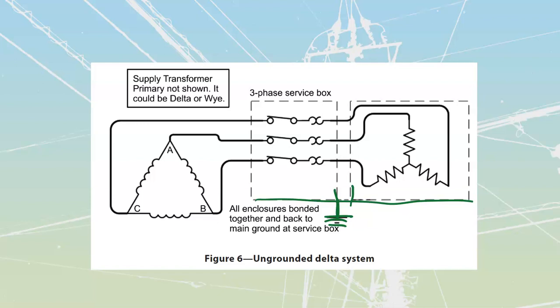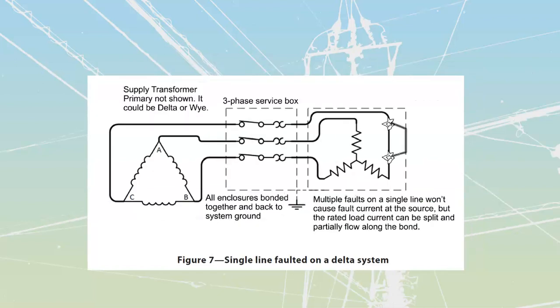Taking a look at what happens under a fault: if there's a single fault, absolutely nothing happens. The neutral point for the system floats right in the very middle, so these points are all floating roughly above ground, circulating around. If we accidentally ground one of these — say a line makes connection over to the bond itself — there's no complete path for current to flow.